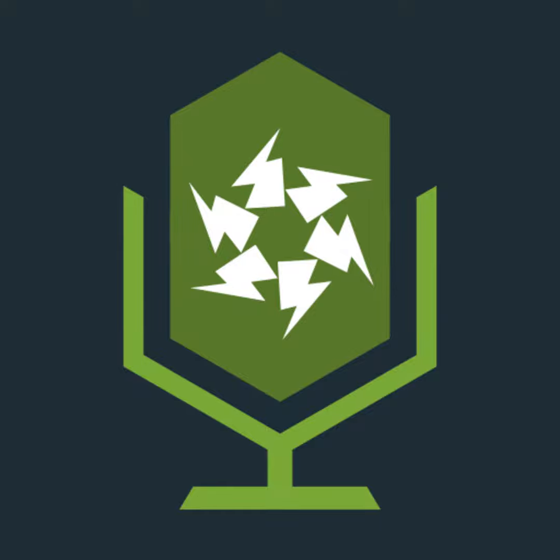It does say, however, "or higher" here, and the advice that Hager have given for this is if you have an MFT that doesn't do a variable, you could just set it to 300 milliamp, which is higher, and as long as the instantaneous disconnection time is within 40 milliseconds, then you're good. So that's a little bit of a way out of this problem. But Hager have received more and more complaints about this issue because it's been very frustrating and confusing for electricians.